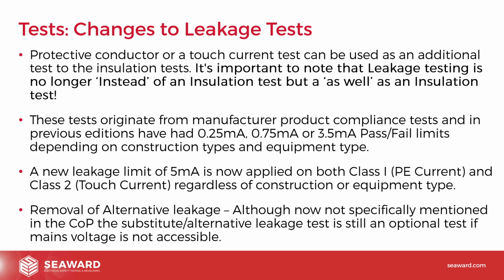Obviously, if you are using a substitute alternative leakage test, you can still use the 5 milliamp figure. You would still use the same pass-fail limit for that. It's just another method of doing it, and the committee felt that it was getting a bit confusing. People were getting confused about what it was saying and why it was different to other tests. So it was decided that it would be removed. Just be aware of that if you're wondering where it's gone. It was removed for that reason.